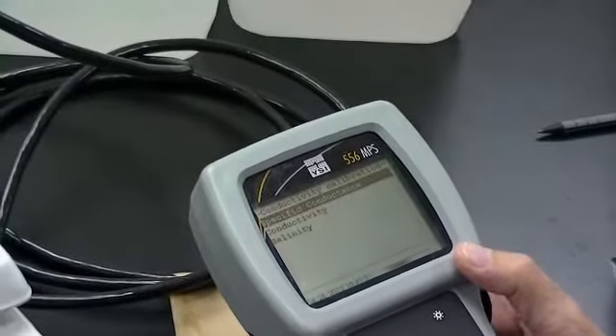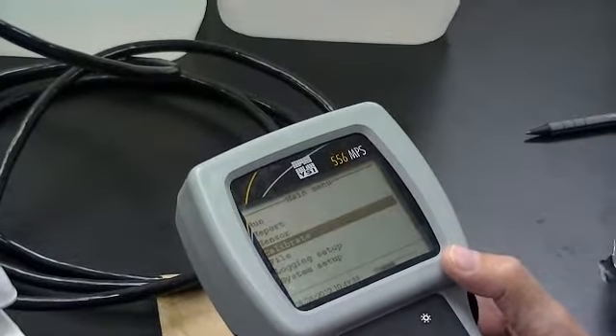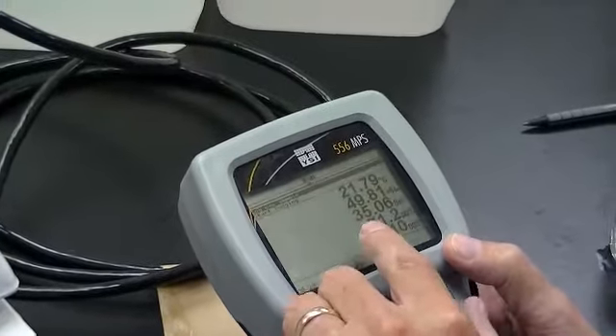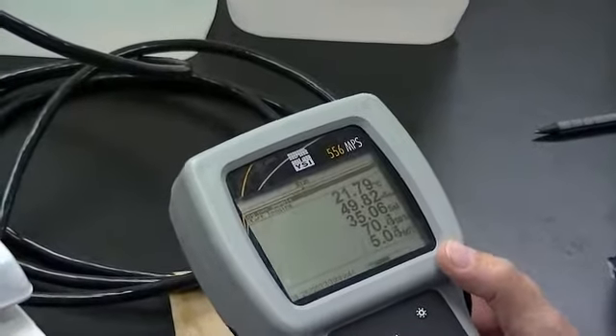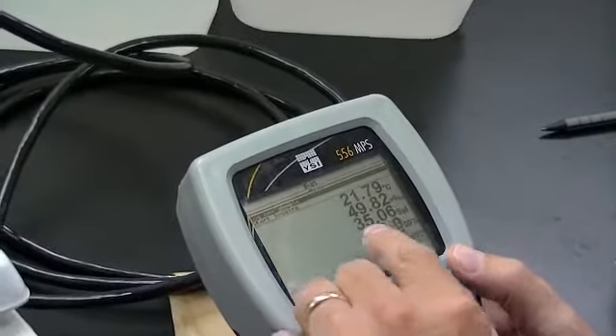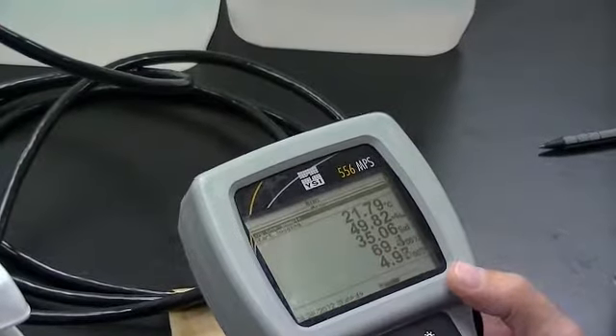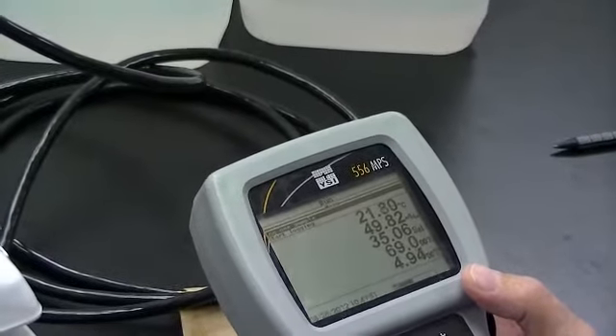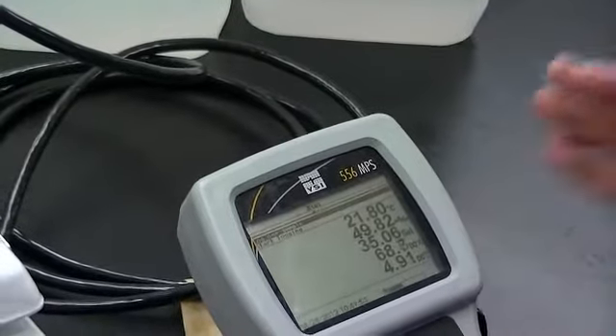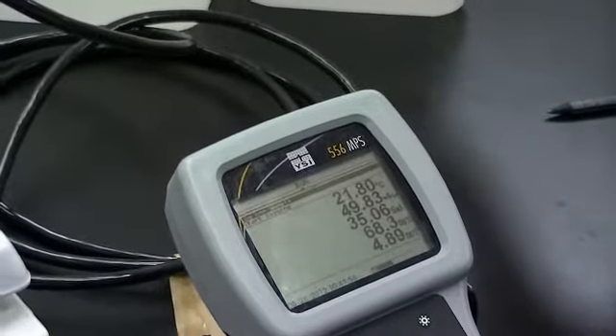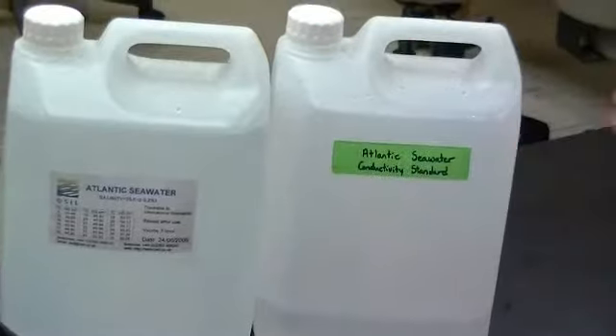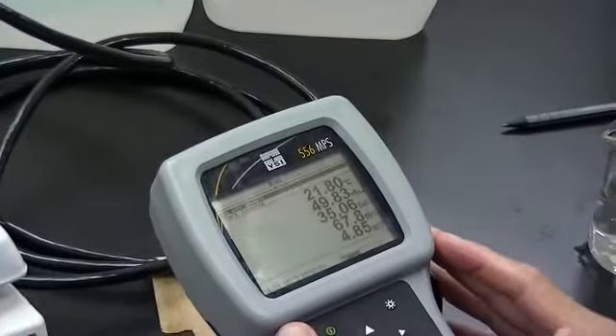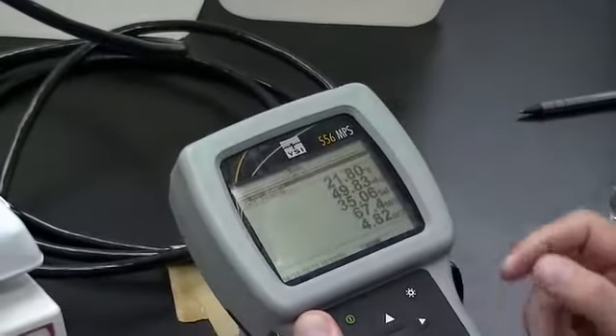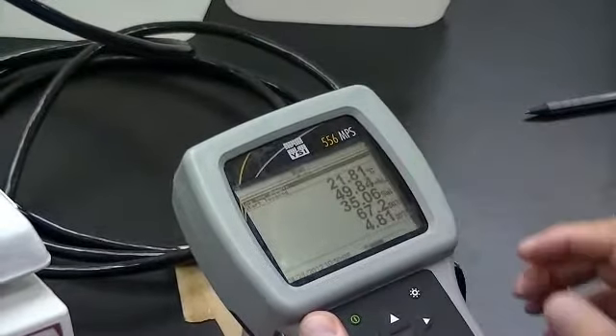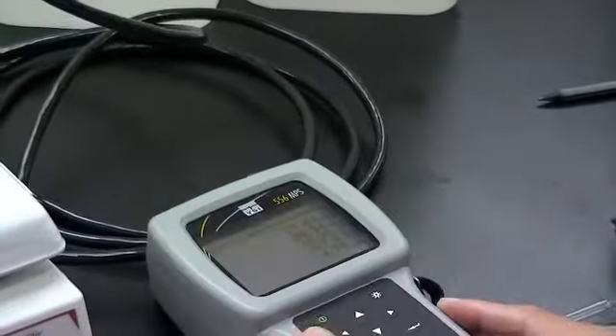And then you can escape back to the start screen. And now you have it calibrated. Now it says 35.06 salinity. Okay? Now that's very close. The salinity of the standard seawater should be 35.0. For this illustration, I used some used conductivity standard, again to save money. But this should be very close to 35. All right, so it is.